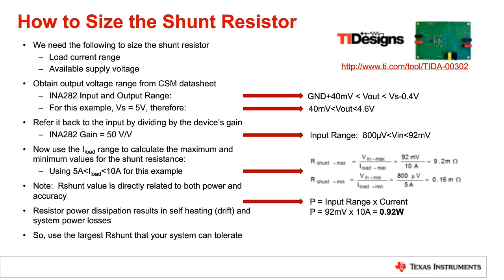And from here, using our load range, so we'll use an example of 5 amps to 10 amps, that's going to get us our actual shunt value using a simple application of Ohm's law. So in this one, we can see at the high end, we have a shunt of 9.2 milliohms, and on the low end, 0.16 milliohms.